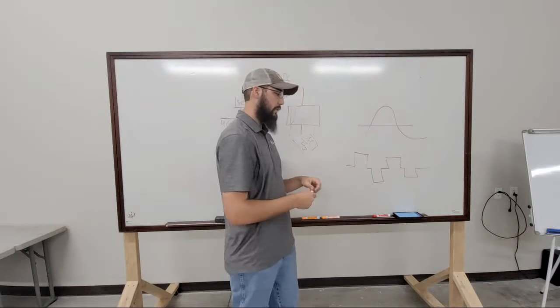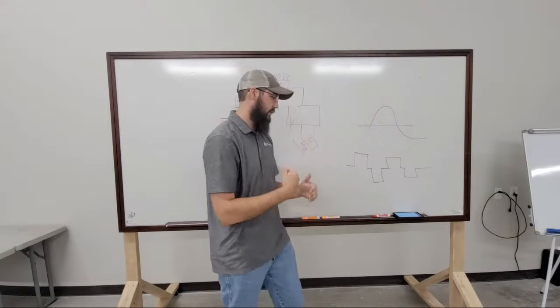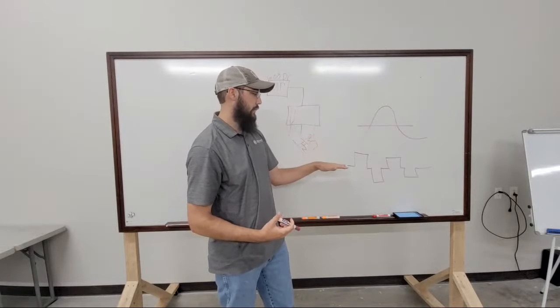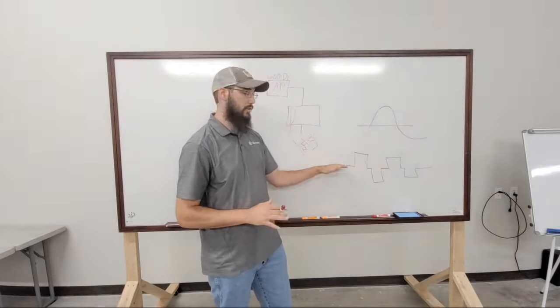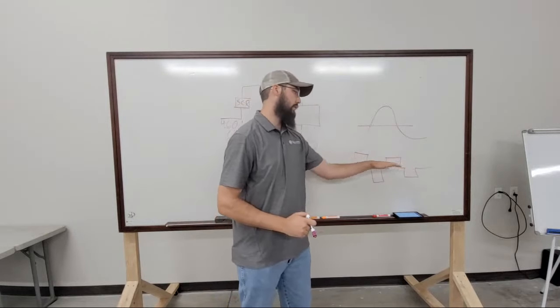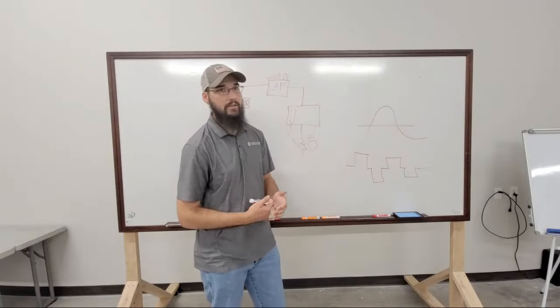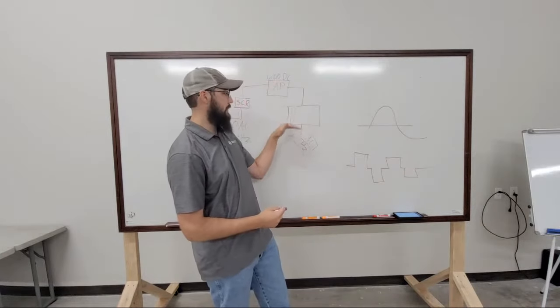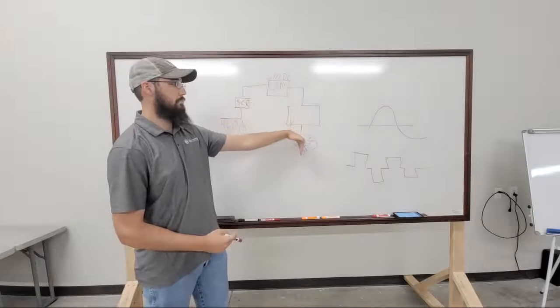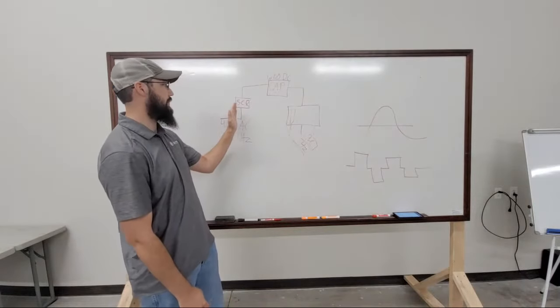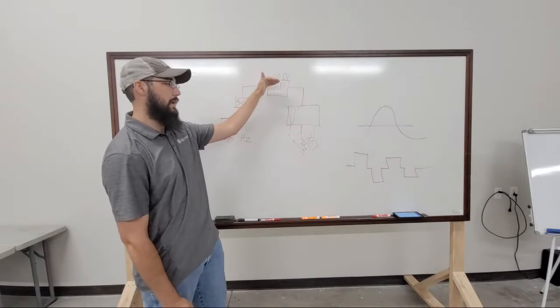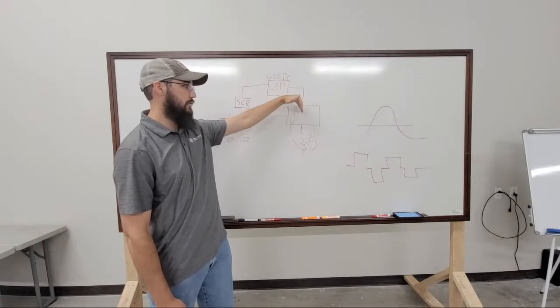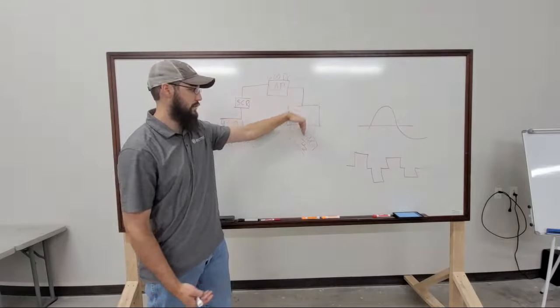One of the things to be aware of is shaft grounding, which is imperative on any kind of drive-driven motor — and that's exactly why shaft grounding is necessary because of those harmonics. That is what the inverter is doing, and that's your full power path going through the drive: 460 AC comes in, goes through the SCRs, hits the capacitor bank, the capacitor bank feeds the inverters, and then the inverter outputs back to the motor through pulse width modulation.